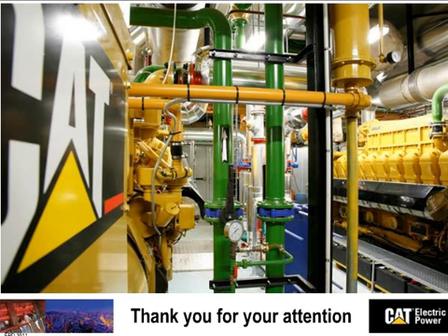Oh, gas pressure. So a gas genset from Caterpillar can take pressure at 100 millibars. So that's typically what we need to have at the engine. Before that, we normally have what we call a gas train. It's a pressure regulator and safety valves, sometimes even a meter. These could take a bit of a pressure drop. Then I recommend that the feeder to the power plant is minimum 200 millibars. That would be nice. 1 bar is fantastic, but it's low pressure.